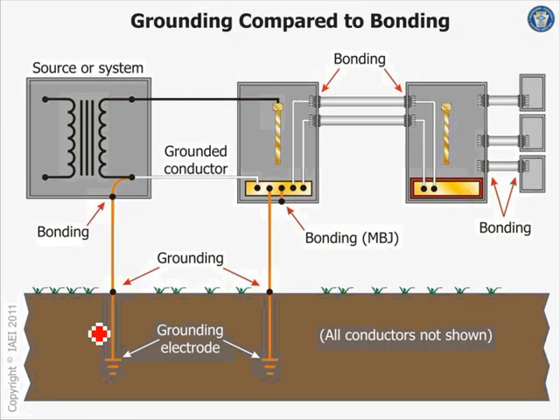So, grounding compared to bonding. When it comes to bonding, the only thing I can think of that is almost uniquely bonding is the main bonding jumpers, right? For example, the main bonding jumper here does the work of grounding though, but it bonds the neutral to the ground, to the enclosure.